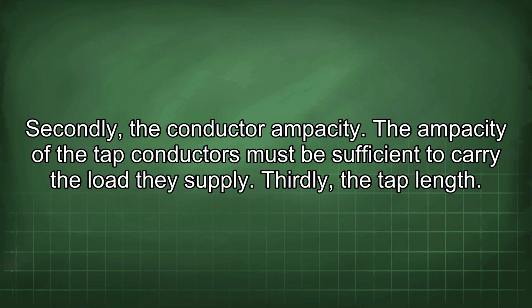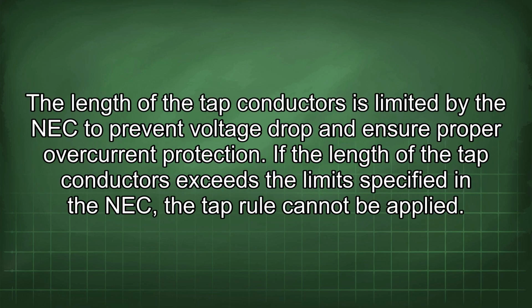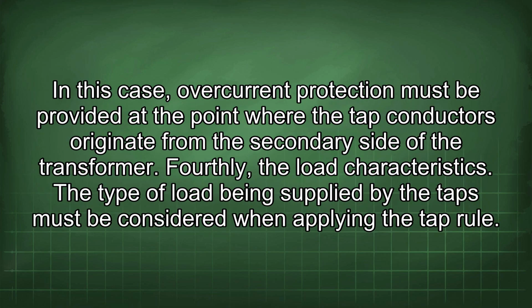Secondly, the conductor ampacity. The ampacity of the tap conductors must be sufficient to carry the load they supply. Thirdly, the tap length. The length of the tap conductors is limited by the NEC to prevent voltage drop and ensure proper overcurrent protection. If the length of the tap conductors exceeds the limit specified in NEC, the tap rule cannot be applied. In this case, overcurrent protection must be provided at the point where the tap conductors originate from the secondary side of the transformer.